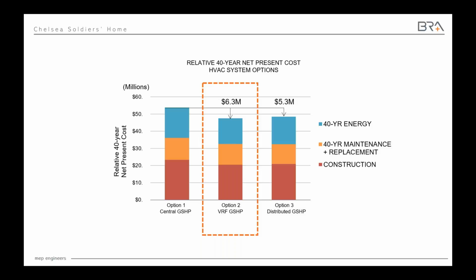On the left, we looked at the central ground source heat pump system with heat recovery chillers in a mechanical room that send chilled water and hot water to the building and use the geo loop as their source of heating and cooling. The middle option was what we had shown in our current design, which is the water source VRF and the heat pump air handlers and so forth. And then on the right was an alternative to that, where we use a heat pump in every single zone, right? Every zone gets its own little heat pump fan coil unit module. And what we found is that the VRF system was the most attractive from a life cycle cost perspective.